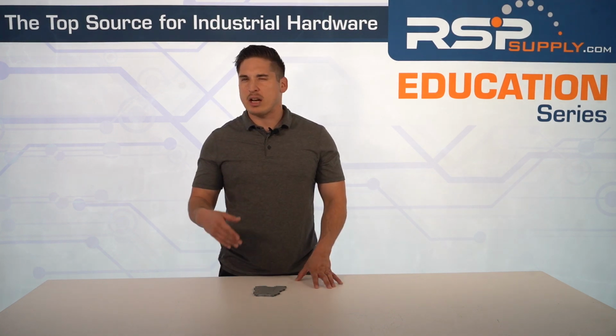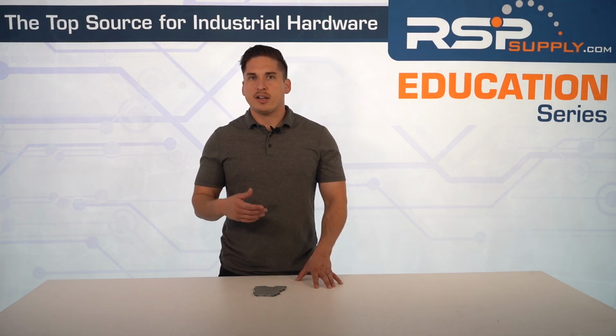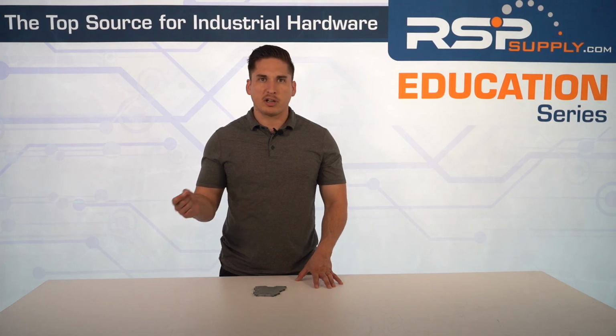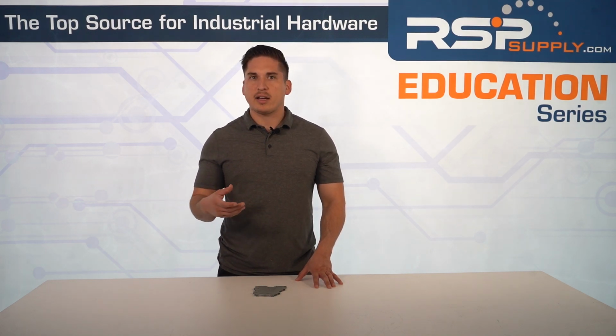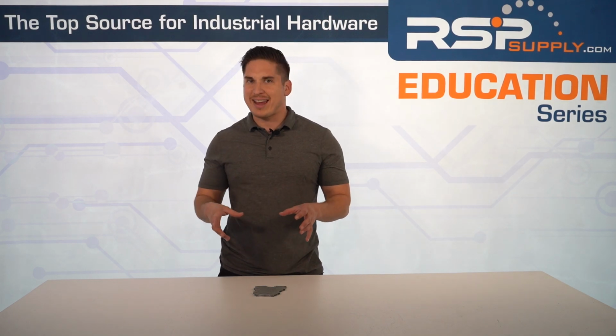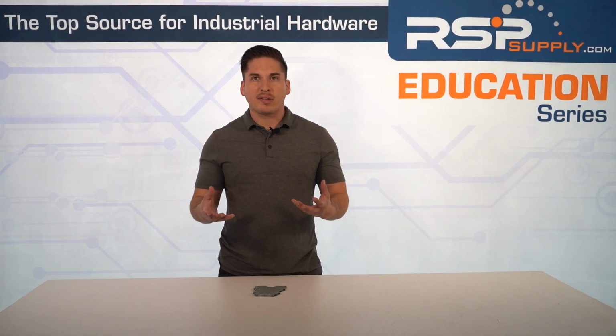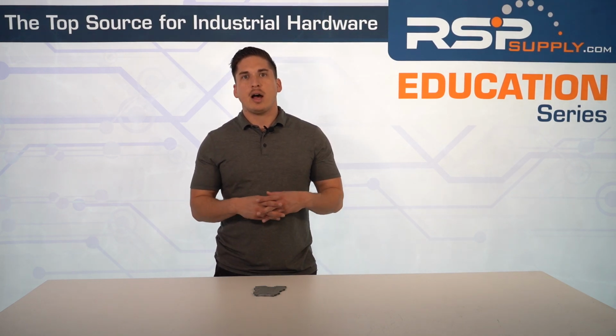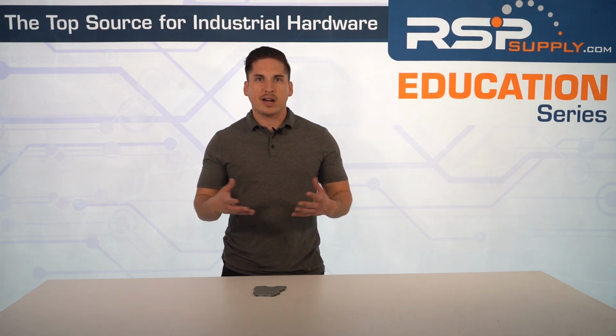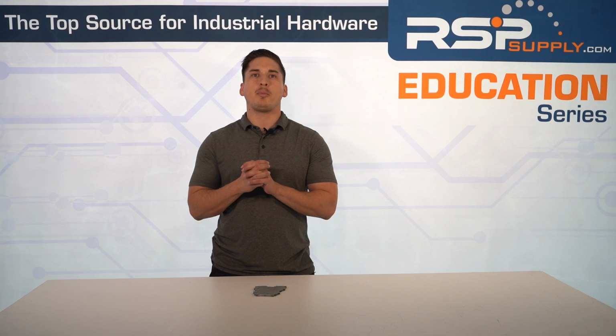Electrical isolation is another task for signal conditioning. It's vital in protecting your system from surges and ground loops. For example, isolating a 4 to 20 milliamp current loop from the PLC input is going to prevent damage from voltage spikes. Multiplexing and signal splitting allow multiple systems to share sensor outputs. This kind of versatility is going to reduce hardware requirements and greatly simplify your panel design.